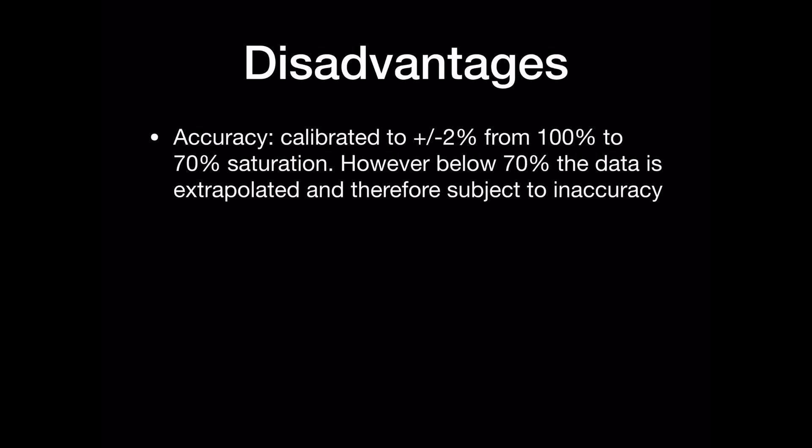There are some disadvantages however. The pulse oximeter was calibrated to plus or minus 2% from 100% saturations down to 70% saturations in healthy volunteers. However, it was felt unethical to measure saturations lower than 70% and therefore the data is extrapolated and subject to inaccuracy at lower levels.